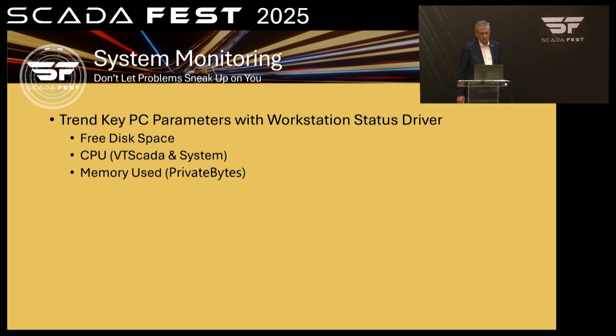System monitoring. This is one that we see people getting bitten by a lot. Don't let problems sneak up on you. Watch for disk space. You can put the workstation status driver as a tag in VT-SCADA that will measure things like disk space, CPU, and memory. And you can put alarms on that. So if your disk space goes too low, you can watch it and say, oh, that shouldn't be this low, or I better buy another hard drive, because if you run out of disk space, you're down on that machine.